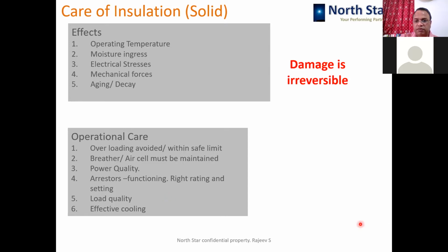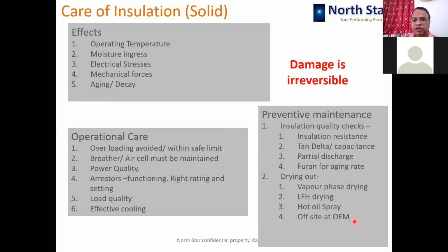So as a preventive maintenance point, we must be checking the insulation quality. At best, we can do all the advanced tests like furan, partial discharge, tan delta and capacitance, and insulation resistance. Out of these, insulation resistance is very, very cheap, and it should be done regularly. All other tests, depending upon the transformer size and severity of the application, have to be performed. Partial discharge can be done on transformers above 33 kV. Furan or aging rate can be done on very old transformers, more than 15 or 20 years of age. Tan delta and capacitance you can do on transformers, but primarily on EHV transformers.